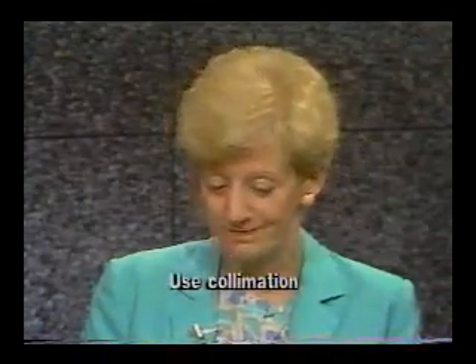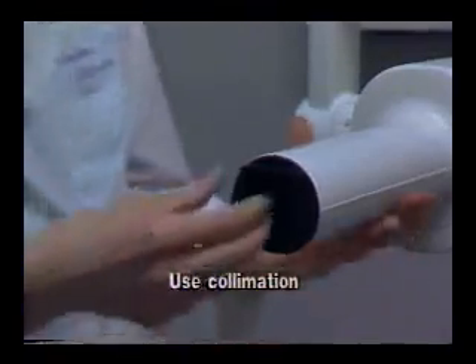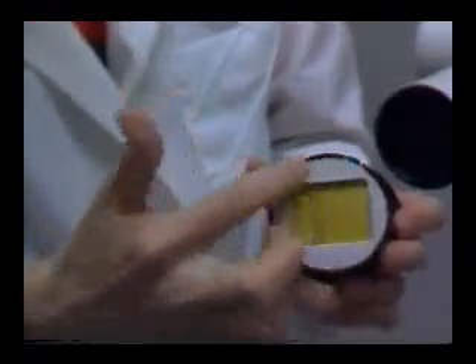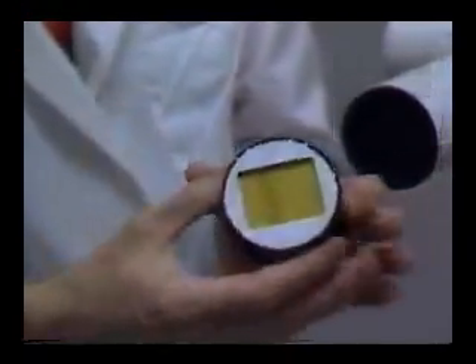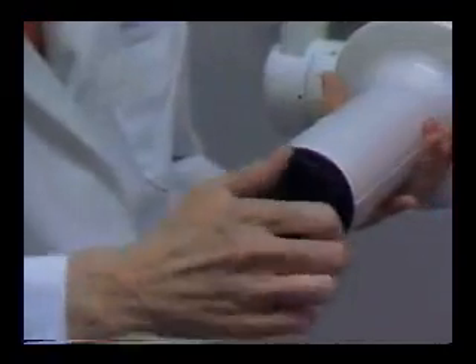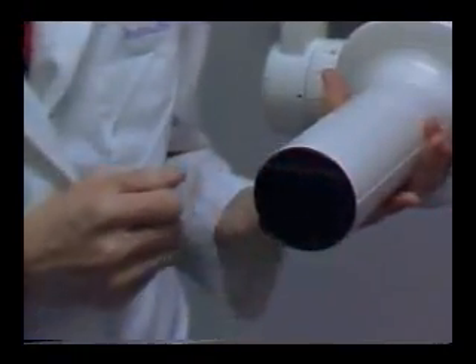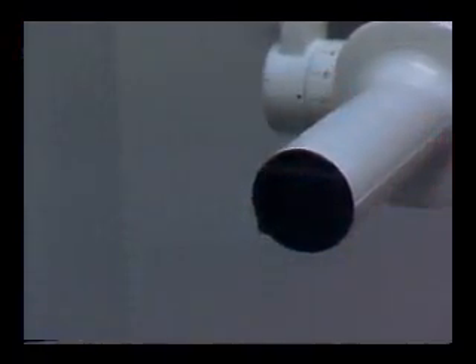The second method for decreasing patient exposure and improving the film is proper collimation. Collimation means that the X-ray beam is limited to the area requested by the doctor. Limiting the size of the X-ray beam reduces exposure of the patient, including to the critical organs, such as the reproductive organs, the eye, and the thyroid gland. Most modern dental radiographic machines are designed with collimators that automatically reduce the beam to the size of the film.